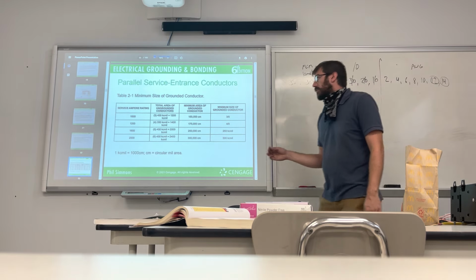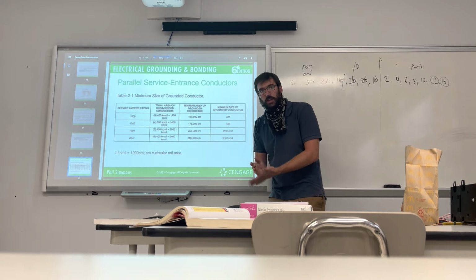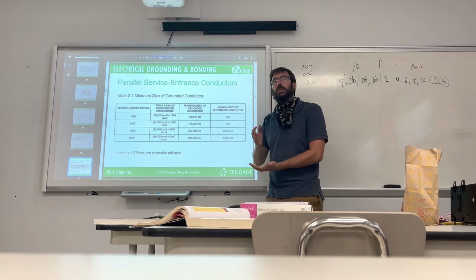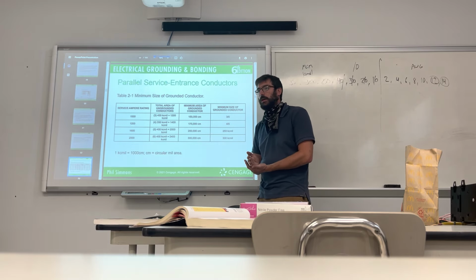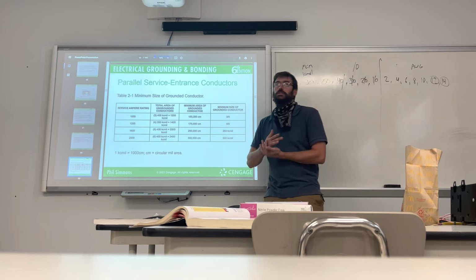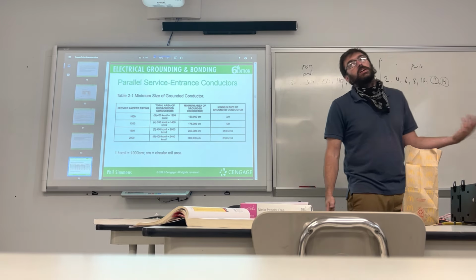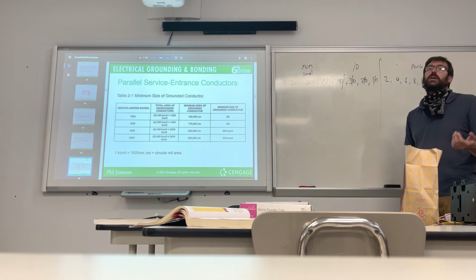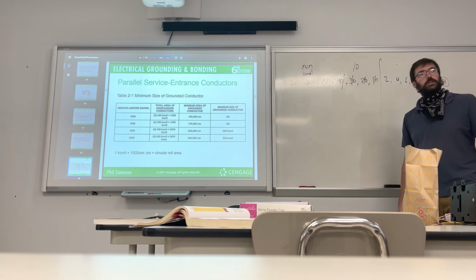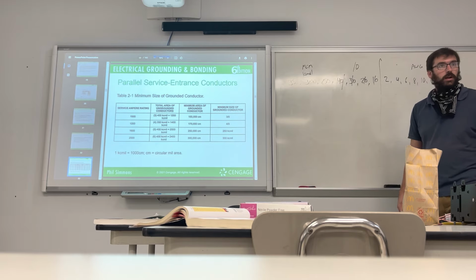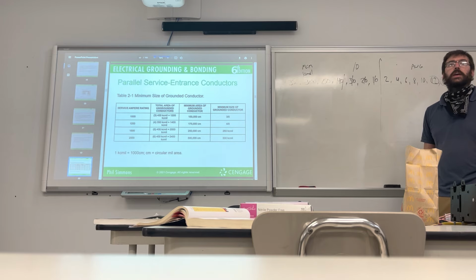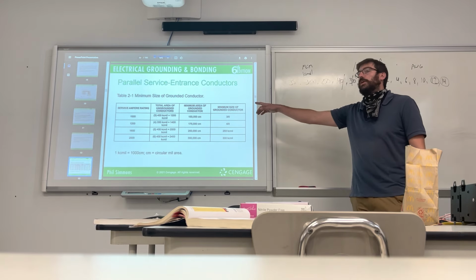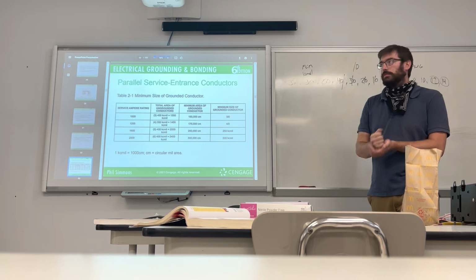The only faux pas is that these wires have to be the exact same length. They have to be the exact same length. Even a foot can start causing problems. Because electricity takes all paths, but does not take them evenly. You know what I mean? If I have a 4-aught wire, a 12 gauge wire, and a 22 gauge wire, they're all vastly different sizes. And I can guarantee that if I touch the 12 gauge versus the 22 gauge, I get bit a lot harder on the 12 gauge than I would on the 22 gauge. But power will be present across all of them. So when we start butting them up, they have to be the same length, or that can cause trouble. Just so we know.